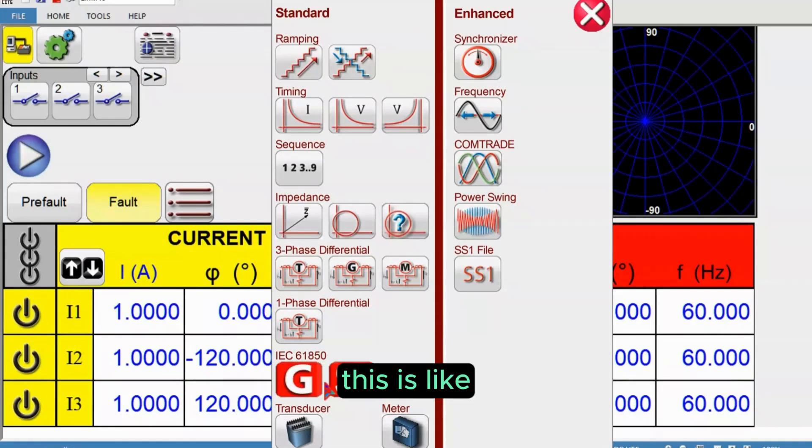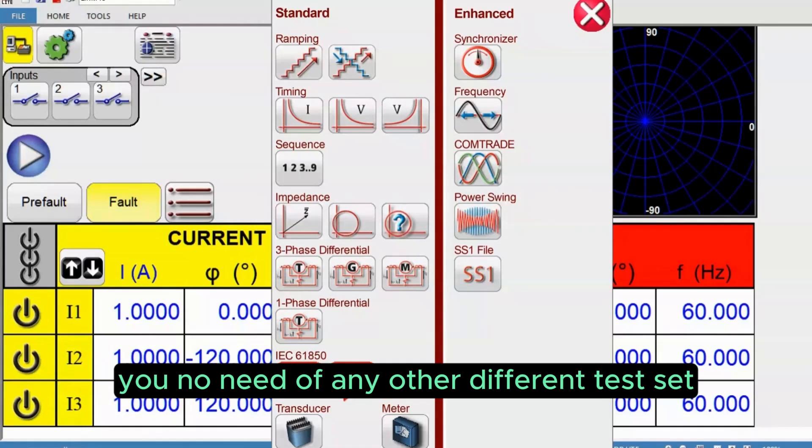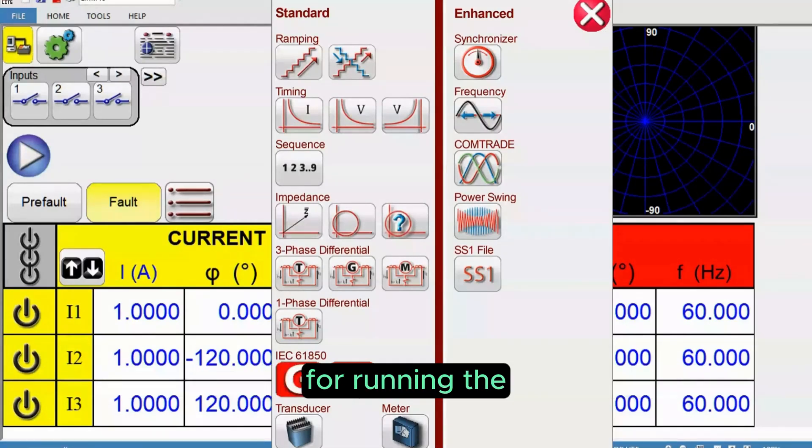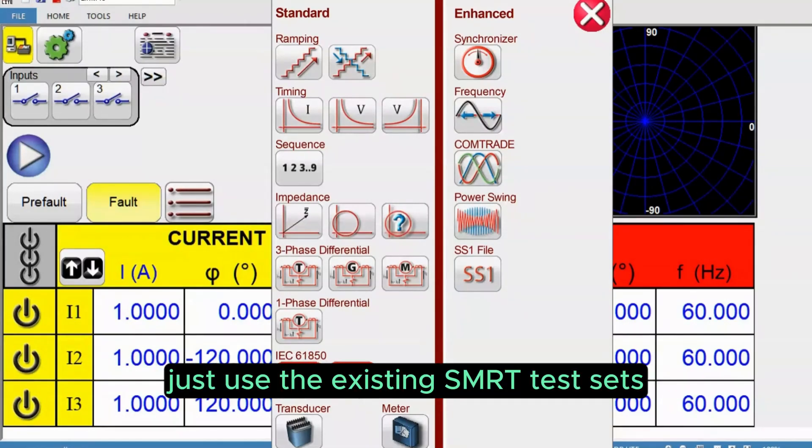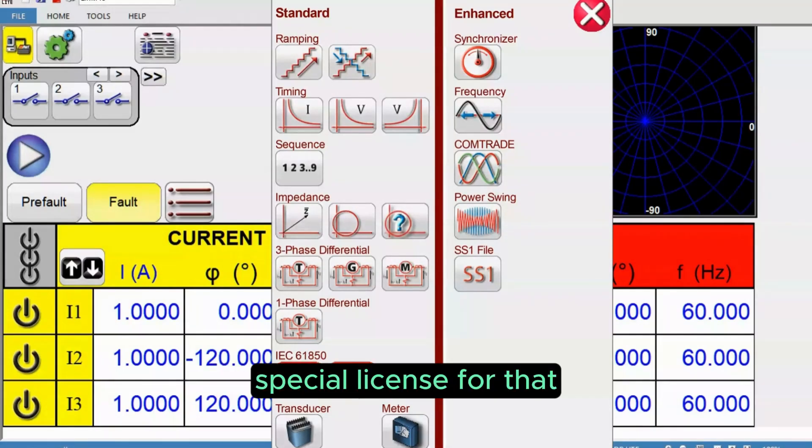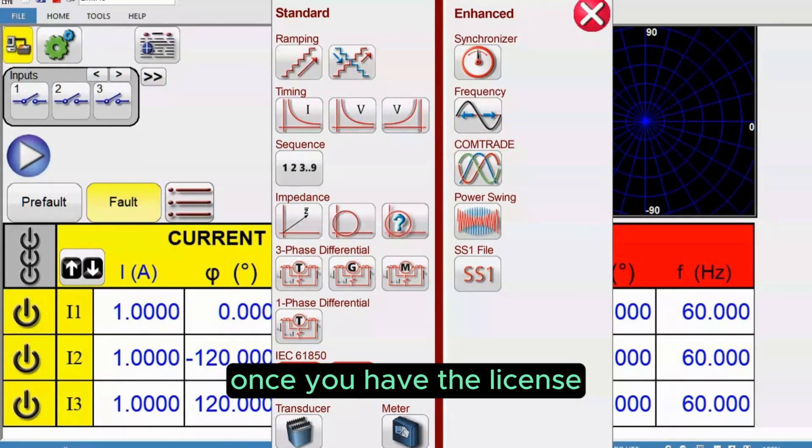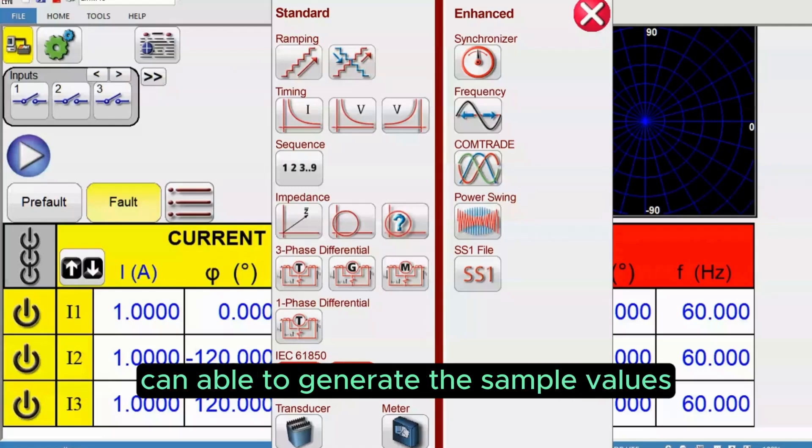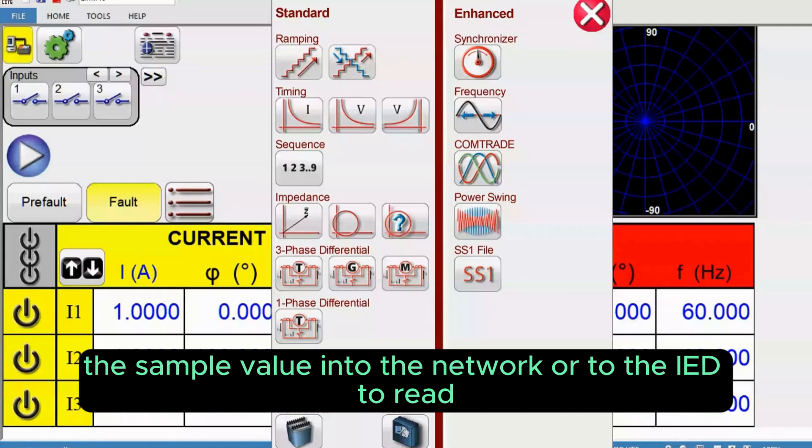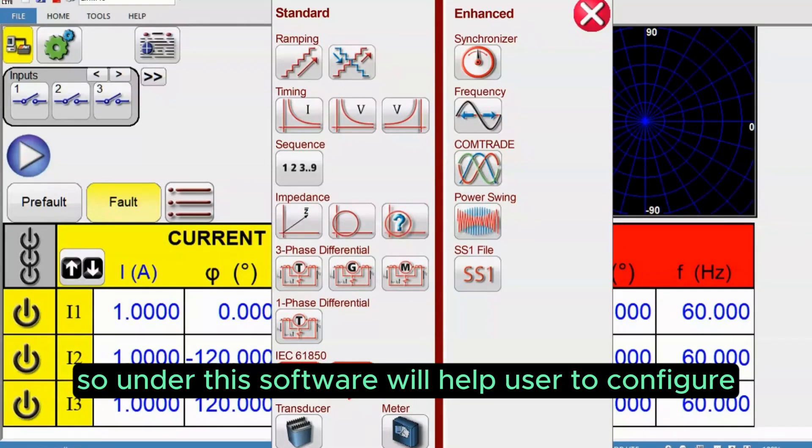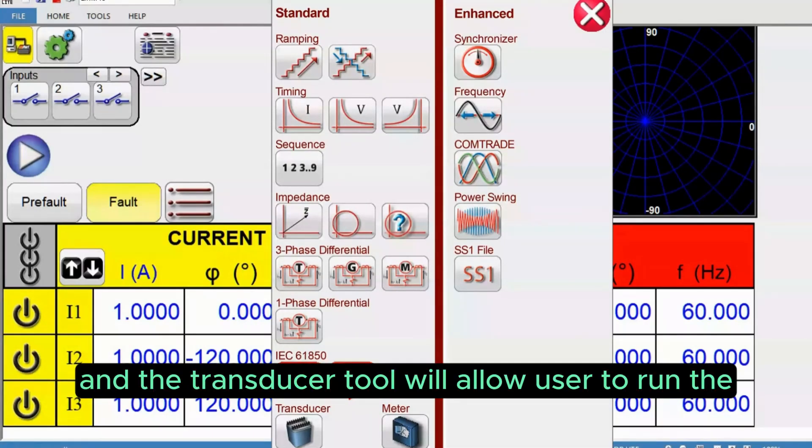The sampled value software allows users to generate sampled values from the same test set. You don't need any other different test set for running or creating sampled values, just use the existing SMRT test set. You need a special license for that. Once you have the license, the analog test set can generate sampled values then publish them into the network or to the IED.